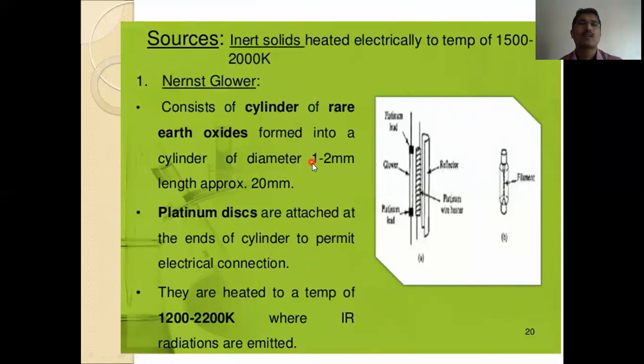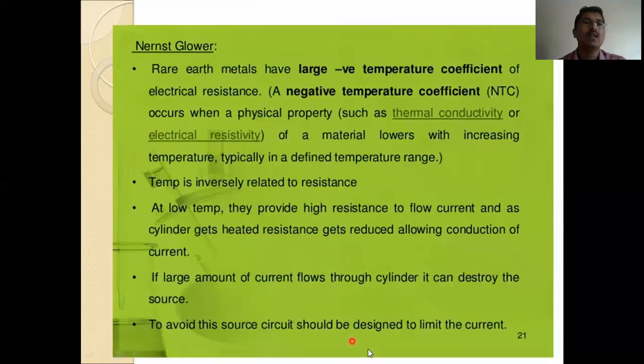Vibration modes. That is the sources. Inert solids heated electrically to temperature of 1500 to 2000 Kelvin. Nernst glower, you can observe here, that consists of a cylinder of rare earth oxides formed into a cylinder of diameter 1 to 2 mm length approximately 20 mm. Platinum discs are attached at the end of the cylinder to permit electrical connections. They are heated to a temperature of 1200 to 2200 Kelvin, where IR radiation are emitted.